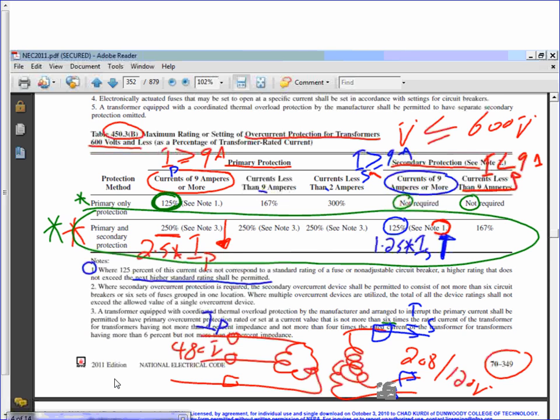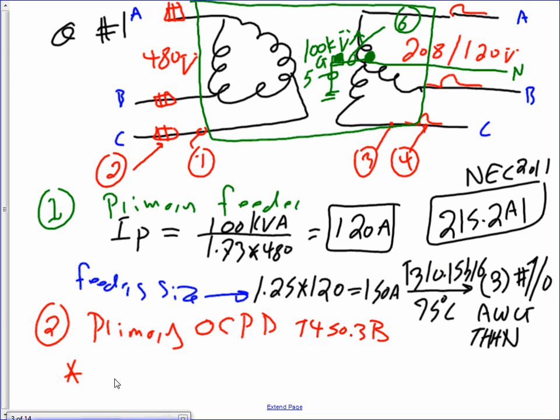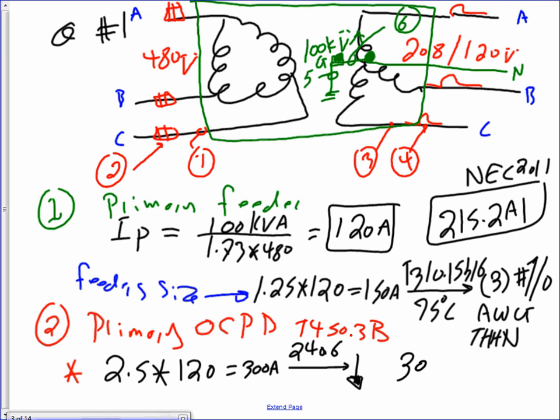Okay. Having said that, so on the primary side, my friends, the multiplier that you're going to be using is 2.5. So primary overcurrent protection device. My multiplier is 2.5 multiplied by 120, and that will give me a healthy 300 amp. And if I have no idea what size this is, you go to 240.6, and if it's not a standard, you have to go down. We just said that, and we hit the jackpot here, and my fuse would be 300 amp.